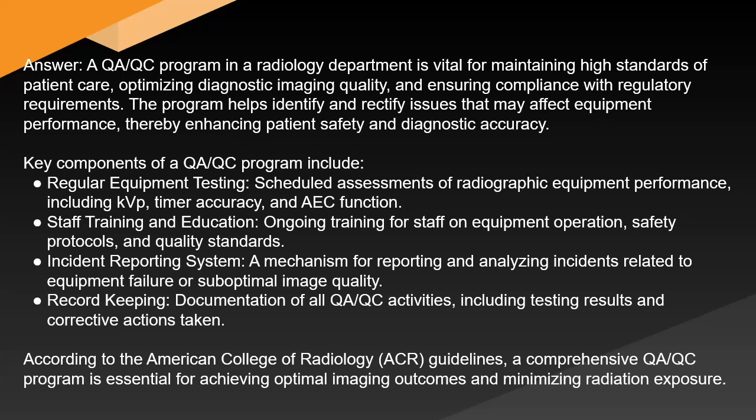The program helps identify and rectify issues that may affect equipment performance, thereby enhancing patient safety and diagnostic accuracy. Key components of a QA/QC program include regular equipment testing, scheduled assessments of radiographic equipment performance, including kVp, timer accuracy, and AEC function, and staff training and education, ongoing training for staff on equipment operations, safety protocols, and quality standards.